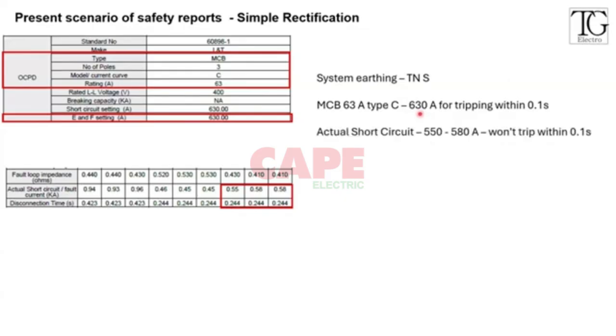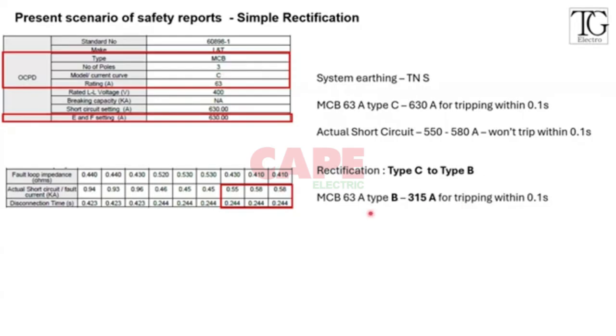So how do you rectify it? The only simple rectification in this test report is to change the type of MCB, the curve, from C type to B type, and that is more than enough. A B type is 5 times, so 5 into 63 is something around 315 amps. If you put a B type MCB, whenever the fault exceeds 315 amps, it is going to trip. In this case, since the fault is 500, it is going to trip. So these are very, very simple rectifications which can be done in the industry.